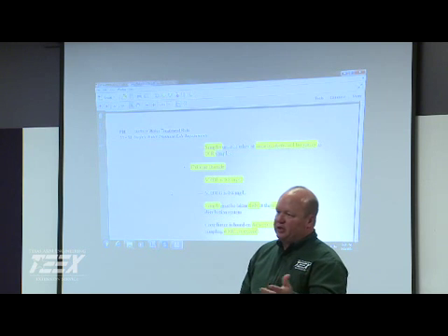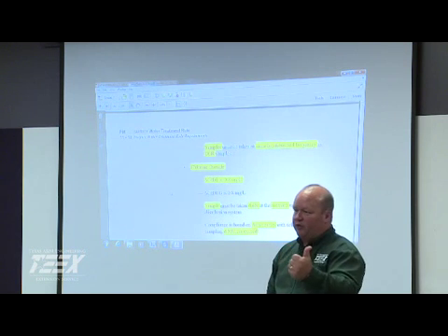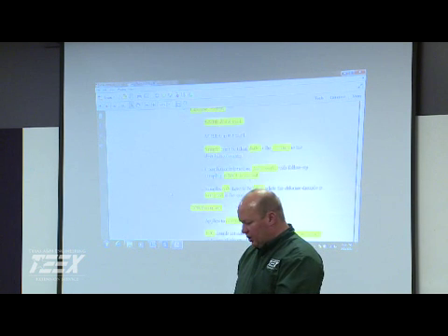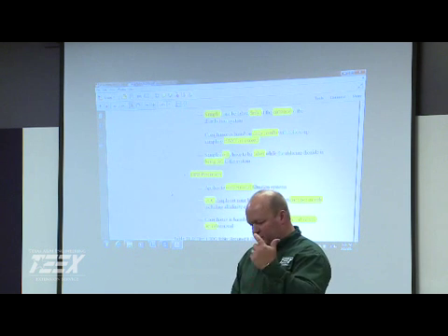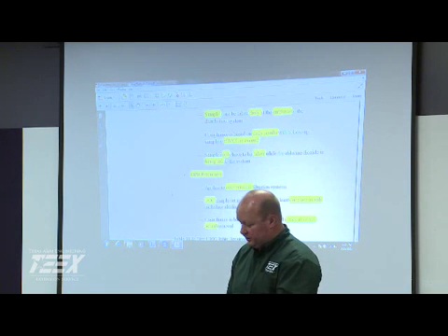Chloramines is the same as chlorine on the 4.0. They're looking at an annual average, and then you have to sample that just like you would your chlorine out in the system. Wherever you're pulling your bacteriological samples, you have to do your residuals there. This is a little bit about the chlorine dioxide. If you do exceed it, you're going to be doing a lot of testing.